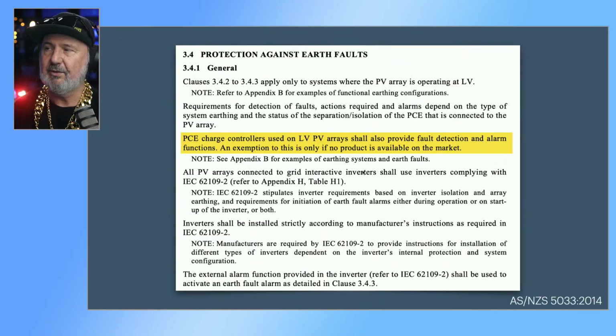We jumped through to the 2014 edition. Additionally, they've specifically mentioned PCE charge controllers, often called regulators, things like maximum power point tracking charge controllers that operate with an LV PV array, shall also provide fault detection and alarm. Now that's a big change. So 2014, which is not yet referenced in the New Zealand electricity regs, but it's long been referenced in Australia, and we've kept this in all the later versions. Every MPPT or charge controller that's got an array operating at LV, that means over 120 volts DC, is required to have an earth fault alarm.